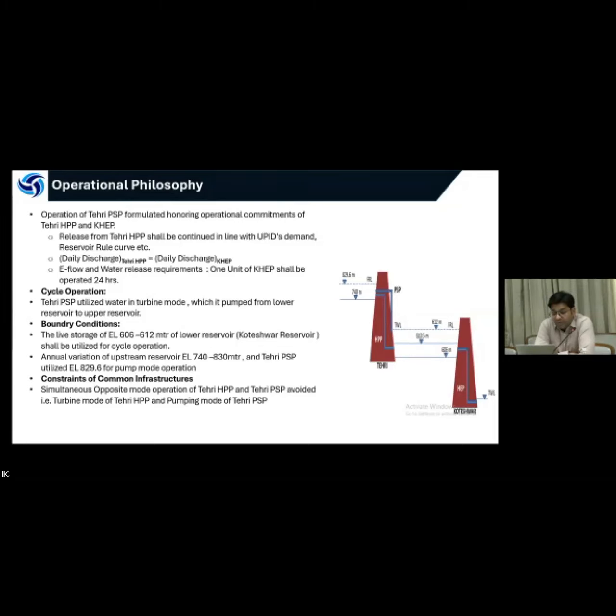Simultaneous operation of the Tehri HPP in generation mode and the PSP in pumping mode is avoided, because both plants are connected through a common bus system and common evacuation system, creating a kind of closed loop. In that case, net output would be insignificant, possibly positive or significantly negative depending on their operating range.